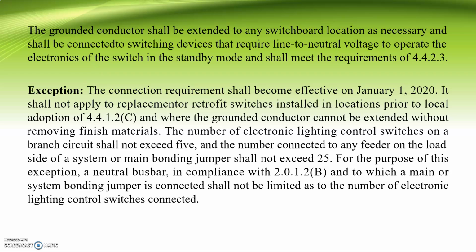So the number of electronic lighting control switches on a branch circuit shall not exceed 5, and the number connected to any feeder on the load side of a system or main bonding jumper shall not exceed 25. So for the purpose of this exception, a neutral busbar in compliance with chapter 2.0.1.2b and to which a main or system bonding jumper is connected.